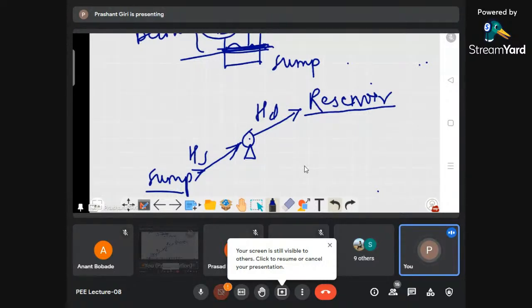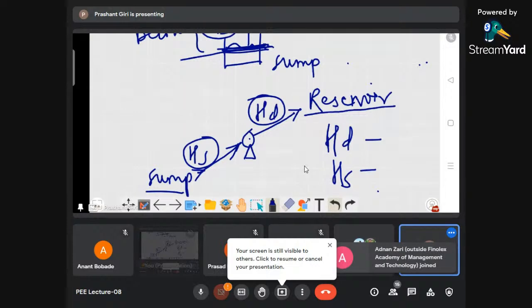आताच आपण शिकलो पाईपलाईन डिझायनिंग. आपल्याला माहित आहे की पाईपलाईनला एक लेंथ असते आणि त्या लेंथ मध्ये लॉसेस होतात. त्यामुळे पंप जेव्हा सक्शन हेड क्रिएट करतो किंवा डिस्चार्ज हेड जनरेट होतो त्यावेळेस ते कुठनं ट्रान्सपोर्ट होतं, फ्लुइड पाईपलाईन मधून. आणि पाईपलाईनचा स्वतःचा रफनेस असेल, फ्लुइडची विस्कोसिटी असेल, पाईपलाईन मध्ये फिटिंग्स असतील, त्यामुळे हे जे हेड आहेत, डिस्चार्ज हेड आणि सक्शन हेड, याच्या पाईपलाईन मध्ये सुद्धा फ्रिक्शनल लॉसेस होतात. बरोबर, व्हायलाच पाहिजे, ऑब्वियस आहे. कारण जर तुमचा सक्शन हेड 10 मीटरचा असेल तर 10 मीटरच्या पाईपलाईन मध्ये लॉसेस होणार. ते लॉसेस सुद्धा तुम्हाला तिथे अकंपनाइड करावं लागेल.